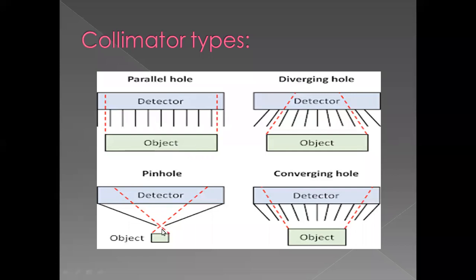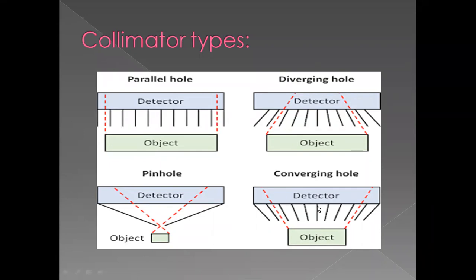We also have the Divergent Hole Collimator, which is used for big organs such as abdominal organs, or for large patients. When we have a small field of view and big organs, we use the divergent collimator. The benefit of this collimator is that it makes the organ look smaller in our image. And we have the last one, the Convergent Hole Collimator, which is the opposite of the divergent. For small organs like the thyroid, the convergent hole will make the gland or organ appear bigger in the image.